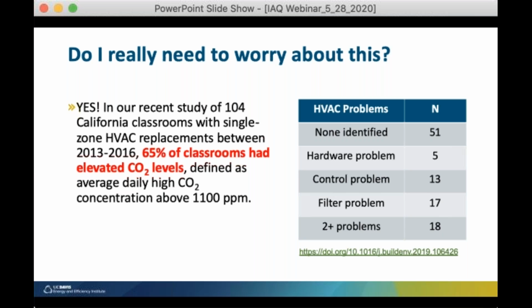Not so fast. In a paper that Theresa and I published in 2019, our team visited 104 classrooms from 11 schools in California. They were all recently retrofitted with new HVAC systems between 2013 and 2016, so relatively new equipment. My team at Berkeley Lab monitored CO2 for 4 weeks in each classroom. We found that in 65% of the classrooms, they had elevated CO2 concentration above the 1100 ppm level. Theresa led a field team that inspected this HVAC equipment. They identified a range of problems: hardware problems, such as inadequate ventilation equipment or improper installation; control problems, such as the fan not operating continuously, leading to not enough outside air being delivered to the classroom when it's occupied; and filter problems, such as filters past due or past their service life. These problems are so common that more than half of the classrooms have one or more.